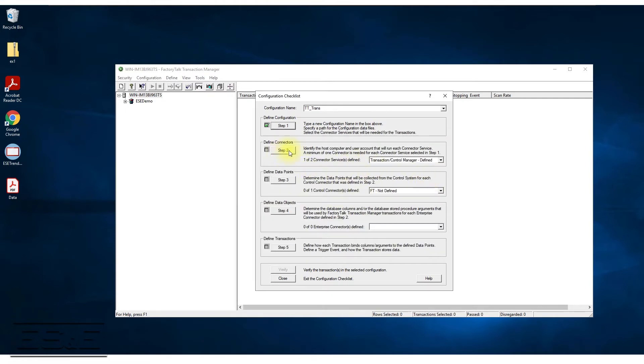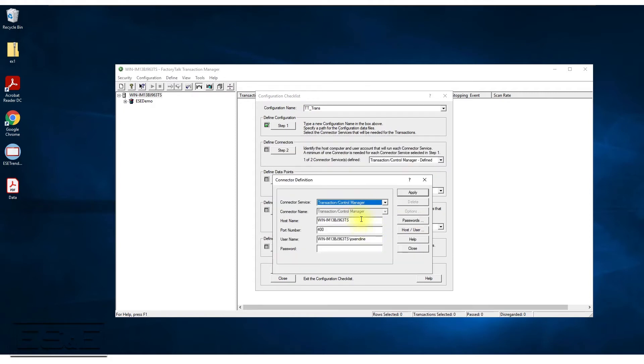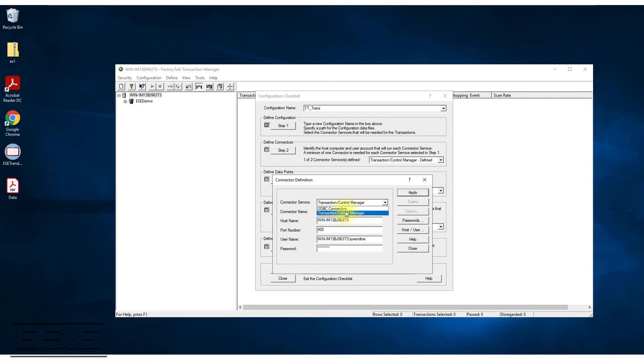Step two is where I define the connectors — mapping to the data points in the controller. Because these connectors run as services, we have to make sure they have passwords to kick those services off. Whatever user accounts you use, make sure they have the rights to turn services on and off. I've defined that I'm going to use the LiveData connector and an ODBC connector, so I need to give an account that can turn on those services.